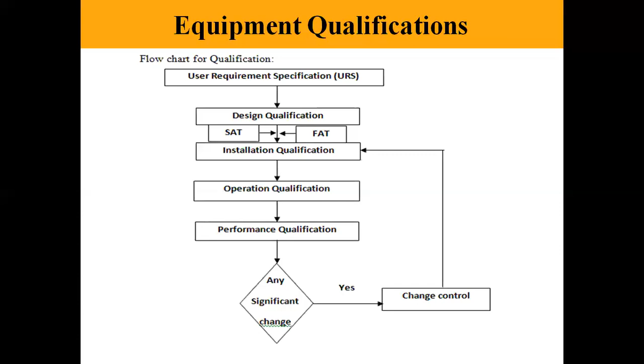Qualification protocols and reports: a protocol and report shall be prepared for each stage of the qualification. Each stage, meaning DQ, should have a protocol and report. After completion of the DQ report, you make a protocol for the IQ. After completion of the installation qualification, you make the report and sign off. Then you make the protocol for the operation qualification, and after completion, you make a report and sign off. Then you make a protocol for the performance qualification, and after completion, you make the report and conclude that this equipment can be used for routine use. The quality assurance personnel shall allot the number for the protocol.